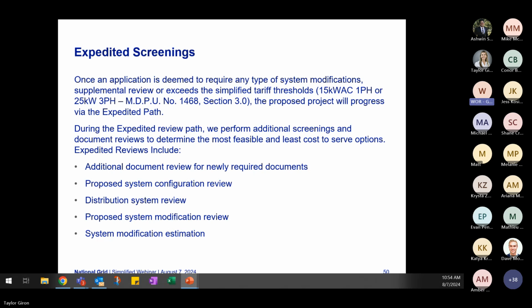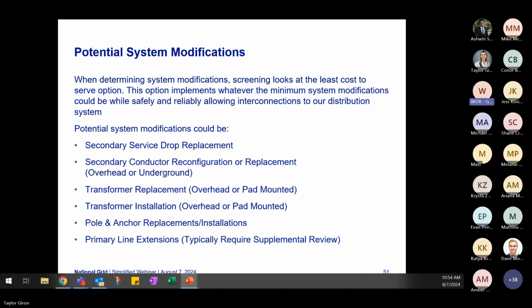When determining system modifications, the screening team looks at the least cost to serve option for our mutual customer. This option implements whatever the minimum system modifications could be while safely and reliably allowing interconnections to our distribution system. Some examples of distribution system modifications include secondary service drop replacement, conductor reconfiguration, transformer replacement or installation, pole and anchor replacements, and primary line extensions, which would require supplemental review.